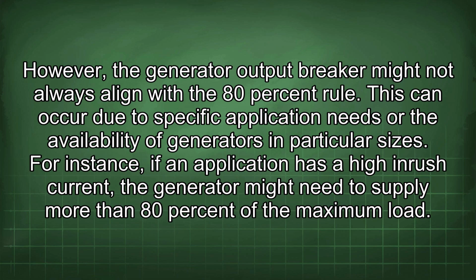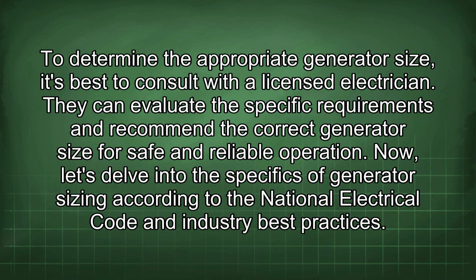For instance, if an application has a high inrush current, the generator might need to supply more than 80% of the maximum load. To determine the appropriate generator size, it's best to consult with a licensed electrician. They can evaluate the specific requirements and recommend the correct generator size for safe and reliable operation. Now let's delve into the specifics of generator sizing according to the National Electrical Code and industry best practices.